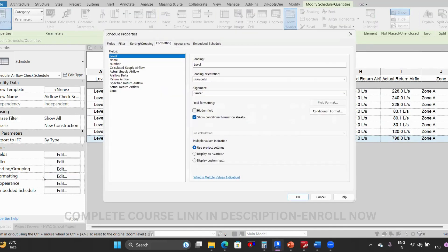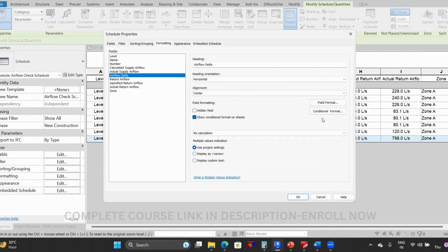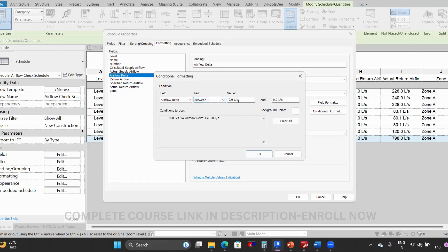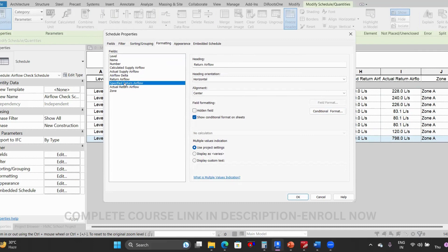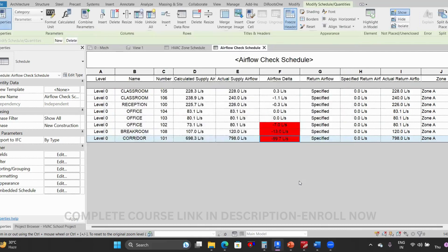For that we have an option called Formatting. Go to the airflow delta parameter and apply a conditional format. Set the condition so that if the airflow delta is NOT between minus 2 and plus 2, apply the color red. This makes it easy to identify problem spaces. We initially set it to 'between' which is the opposite — change it to 'not between,' then click OK.